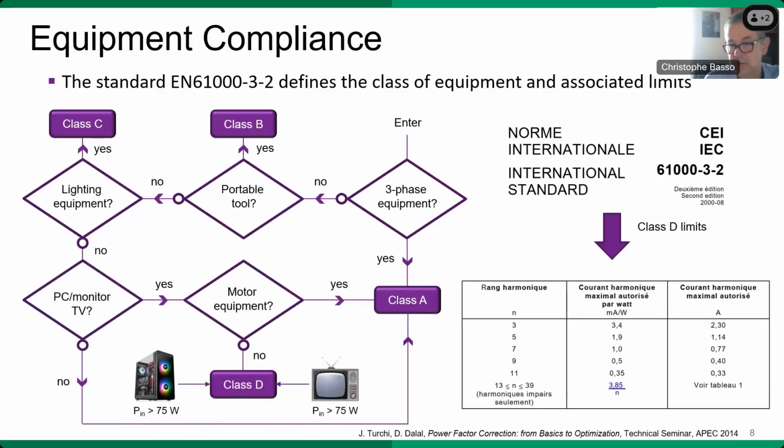There is an international standard that tells you the amount of harmonic that is authorized, and it's going by harmonic content. Actually, it's the IEC 61000-3-2, and it defines the measurement conditions and harmonic limits for the European mains. The harmonization actually took place in other countries like Japan, China, UK, etc. But PFC is not a requirement for US market, for instance. However, many manufacturers do include a front-end converter to reduce the input RMS current to reasonable values.